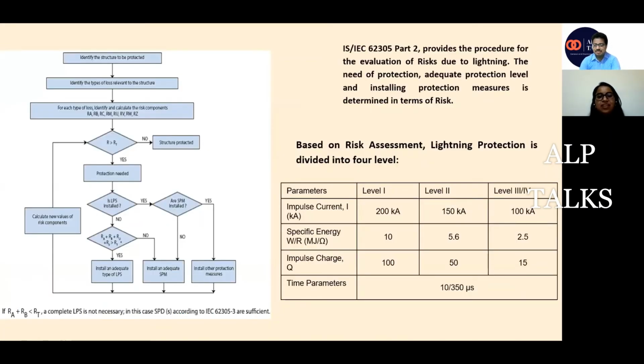Basically, for the lightning protection system, an important role is played by the lightning risk assessment. First of all, we have to do the risk assessment calculation to see whether my structure needs to be protected by a lightning protection system, or it is already protected and we do not need to install any further equipment or system. After that, if it requires lightning protection, the concern is at what level of protection I need to protect my structure. There are a total of 4 levels of protection: level 1, 2, 3, and 4, in which level 1 is the highest prone to lightning, and level 4 is the least prone. So as per the risk assessment calculation, the requirement of lightning protection and the level of protection are decided. After that, we proceed to the designing of the system.